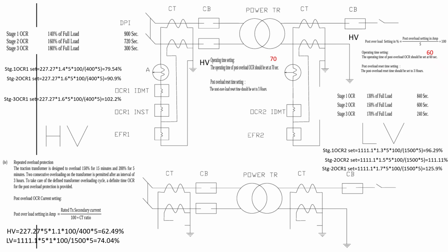Why? Because the direction of the current of the two CTs is reversed. One is incoming and another is outgoing in both the CTs. So polarity will be reversed in the secondary. So through the relay it is connected in series, and after joining the two other ends, we have earthed it.